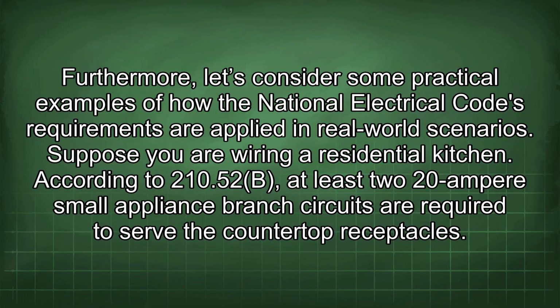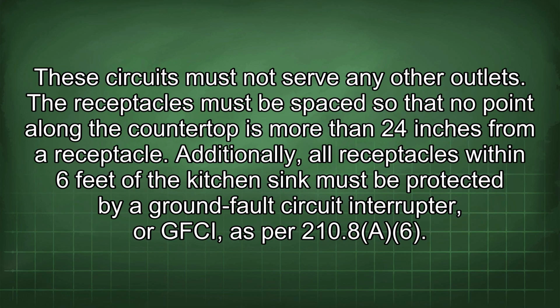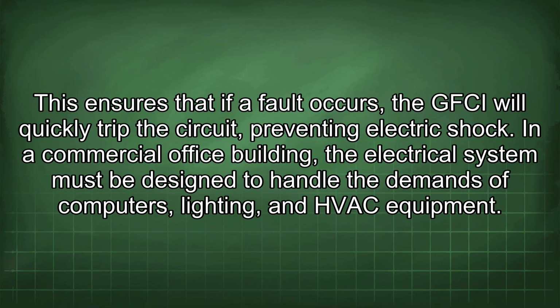Suppose you are wiring a residential kitchen. According to 210.52(B), at least two 20A small appliance branch circuits are required to serve the countertop receptacles. These circuits must not serve any other outlets. The receptacles must be spaced so that no point along the countertop is more than 24 inches from a receptacle. Additionally, all receptacles within 6 feet of the kitchen sink must be protected by a ground fault circuit interrupter, or GFCI, as per 210.8(A). This ensures that if a fault occurs, the GFCI will quickly trip the circuit, preventing electric shock.